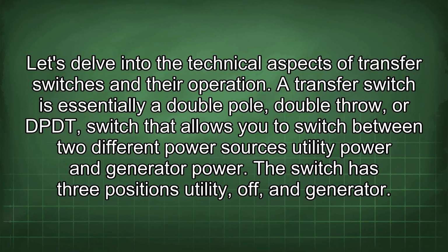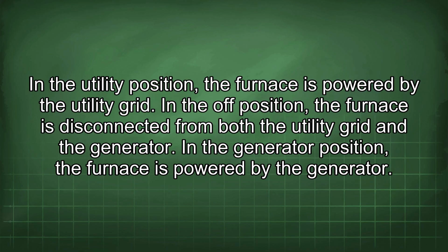Let's delve into the technical aspects of transfer switches and their operation. A transfer switch is essentially a double pole, double throw, or DP/DT switch that allows you to switch between two different power sources, utility power and generator power. The switch has three positions: utility, off, and generator. In the utility position, the furnace is powered by the utility grid. In the off position, the furnace is disconnected from both the utility grid and the generator. In the generator position, the furnace is powered by the generator.